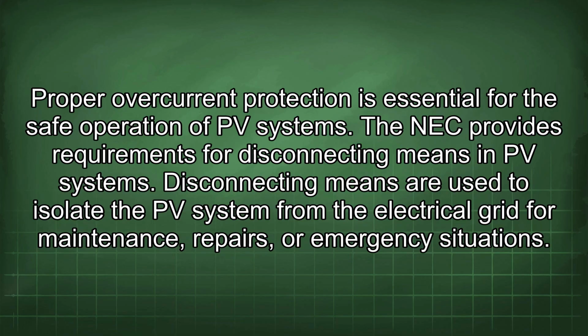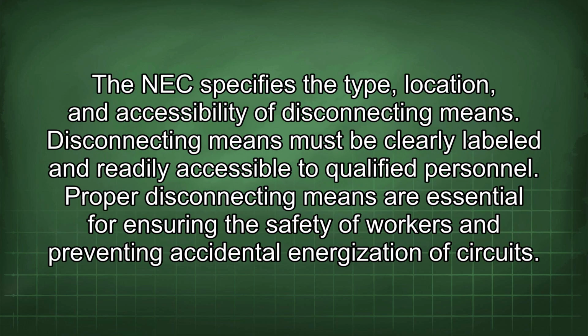The NEC provides requirements for disconnecting means in PV systems. Disconnecting means are used to isolate the PV system from the electrical grid for maintenance, repairs, or emergency situations. The NEC specifies the type, location, and accessibility of disconnecting means. Disconnecting means must be clearly labeled and readily accessible to qualified personnel. Proper disconnecting means are essential for ensuring the safety of workers and preventing accidental energization of circuits.